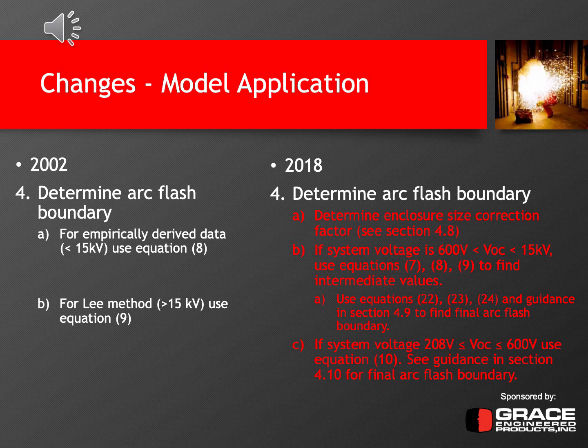So once the incident energy has been determined, like I said, the next step is to determine the arc flash boundary. And in 2002, the arc flash boundary was determined by a simple equation for different voltage levels. The first one was based on the empirically derived data that was taken that was less than 15 kV, and it says use equation 8. For the Lee method, or voltages that are greater than 15 kV, use equation 9.